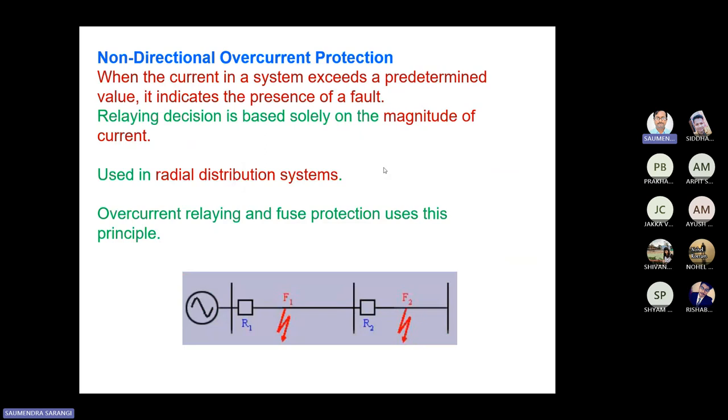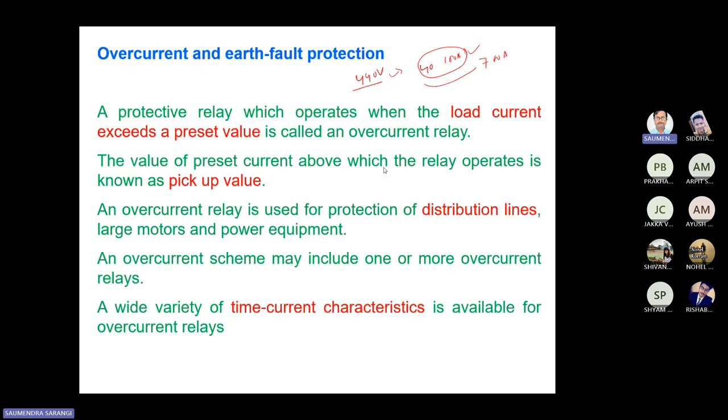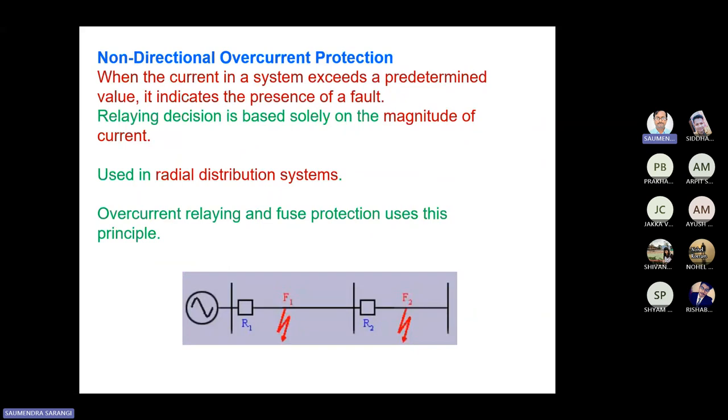Now, in case of our overcurrent relay, this load current is nothing but our reference. Seeing the load current, we have to set the relay. So the pickup value is the value of current above which the relay operates. Means it is the preset current above which the relay operates, and that is called the pickup value.